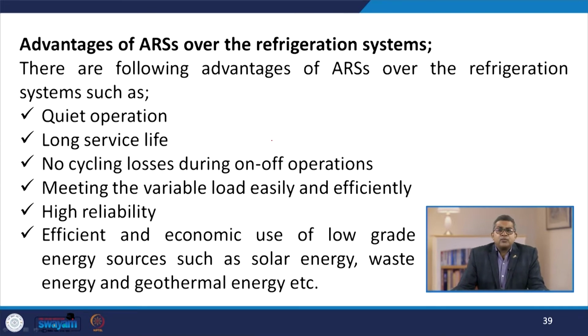The advantages of ARS over the vapor compression refrigeration system: there are different types of advantages attributed to the ARS, such as quiet, noiseless operation, long service life, no cycling losses due to on-off operation, they meet the variable load easily and efficiently, they possess a high degree of reliability, and they are efficient and economic with respect to the use of low grade energy sources such as solar energy, waste energy and geothermal energy.